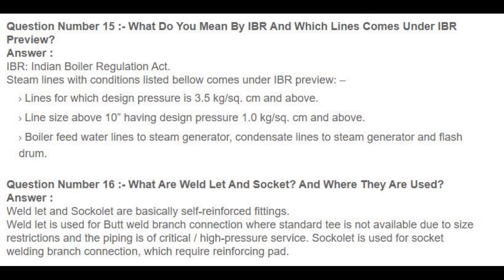Question number 16: What are weld-o-let and socket-o-let, and where are they used? Answer: Weld-o-let and socket-o-let are basically self-reinforced fittings. Weld-o-let is used for butt weld branch connections where a standard tee is not available due to size restrictions and the piping is of critical high pressure service. Socket-o-let is used for socket welding branch connections which require a reinforcing pad.